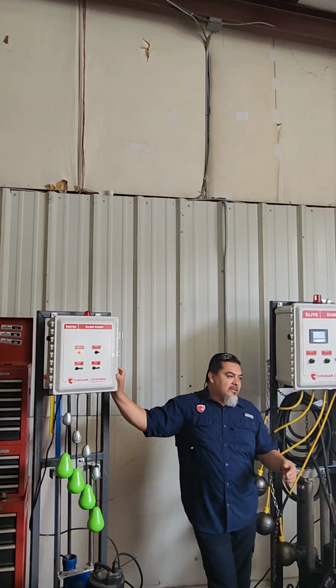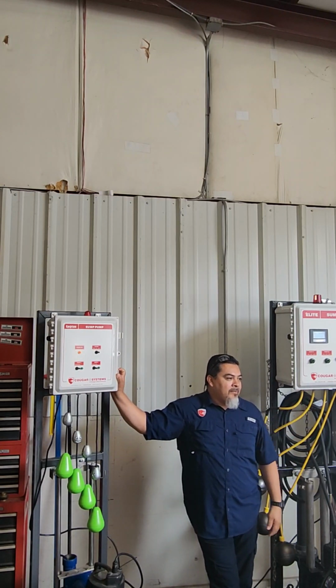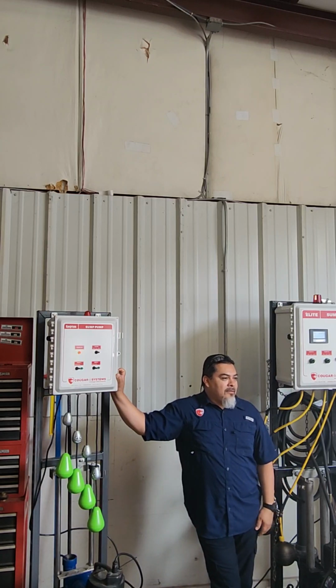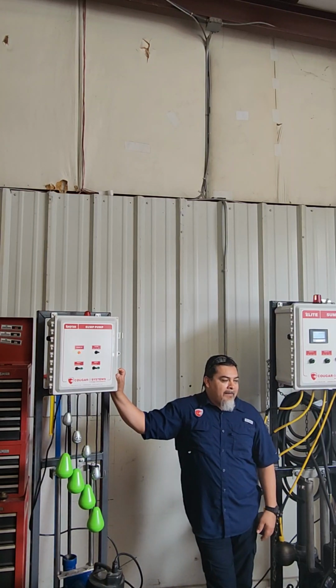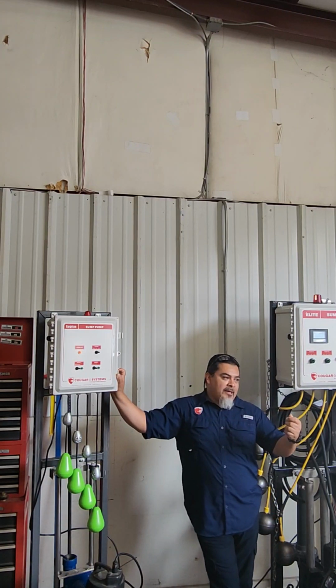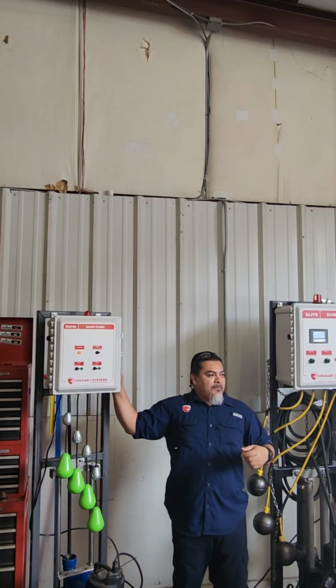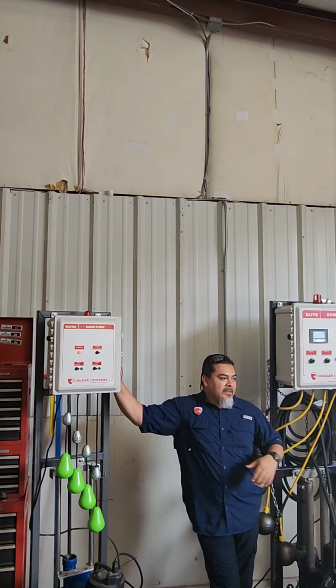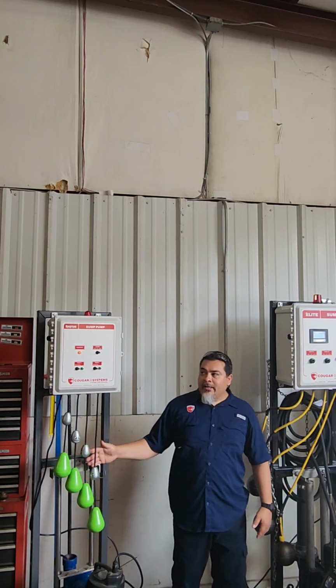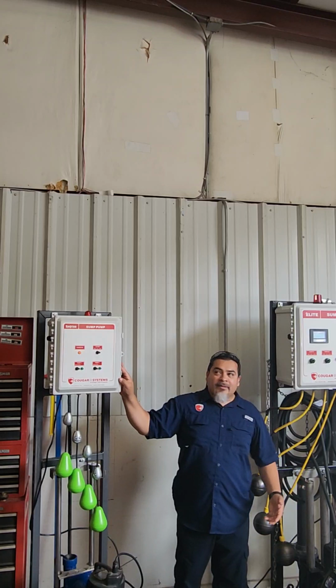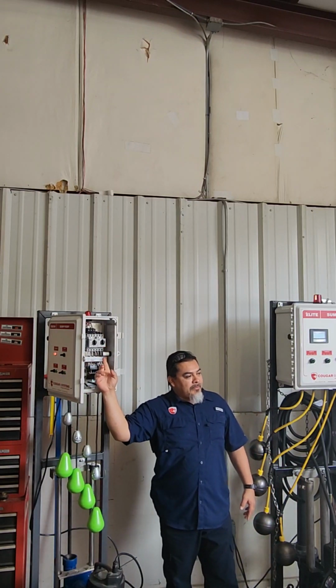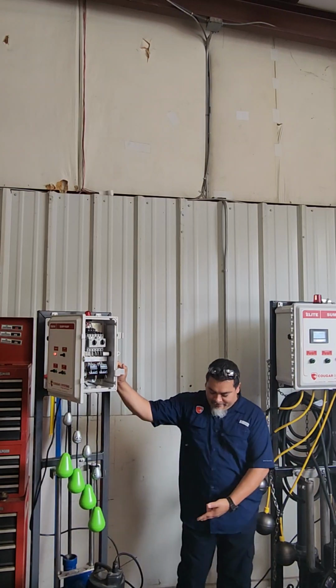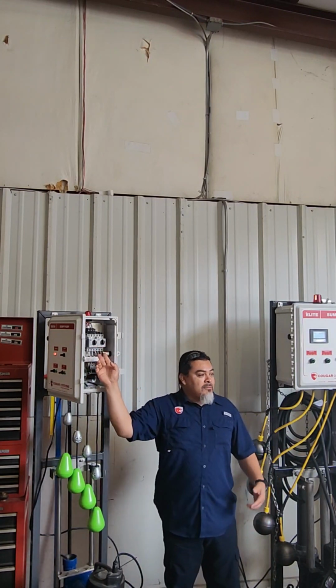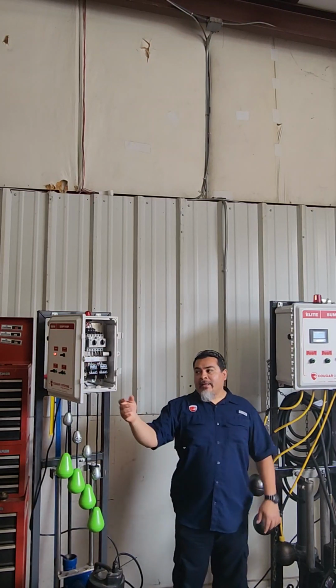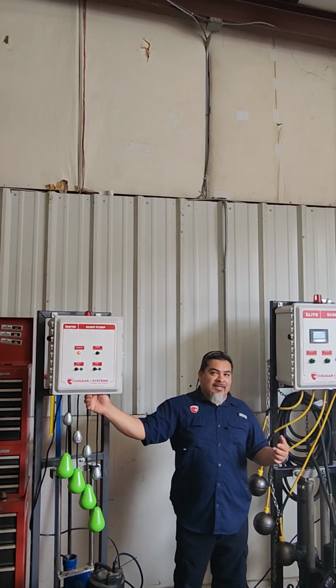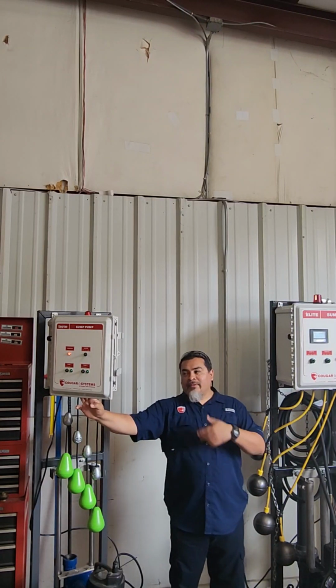Floats. Okay, so when y'all get to the field and put it on hand, does the pump come on? Sometimes, sometimes not. We had problems with the water. So there's a difference. If you bring it on hand and it does operate, that means everything's good in the panel. The overloads are not tripped, the pump can run, it's just out of sight. If for some reason you put it on hand and it don't come on, it's probably because the overload is tripped. That means something's indicating the pump's locked up. So you reset whatever overload there is, whether it's the switches or the button, and then you try it again on hand. And like I said, if it takes like 3 to 4 seconds to retrip, it's jammed.